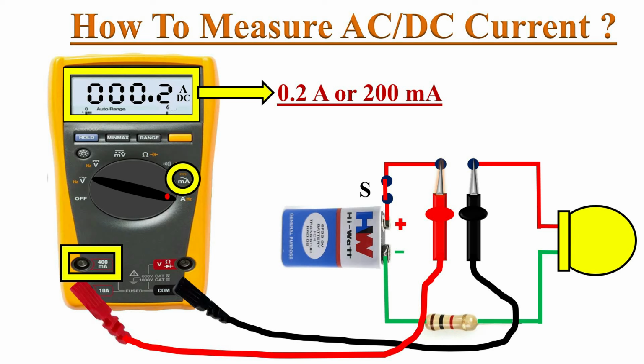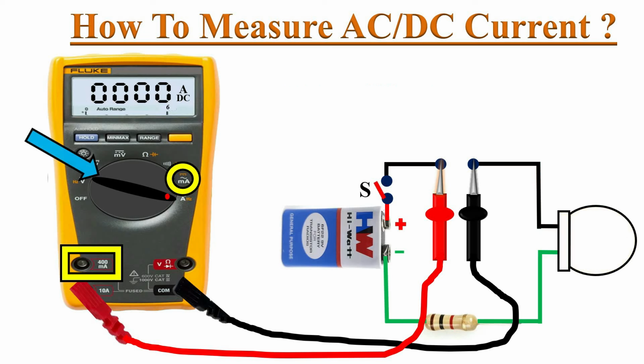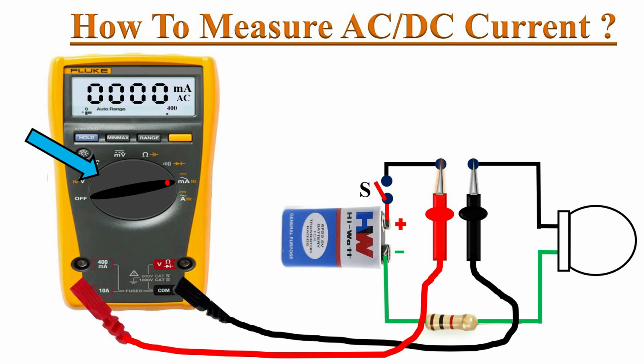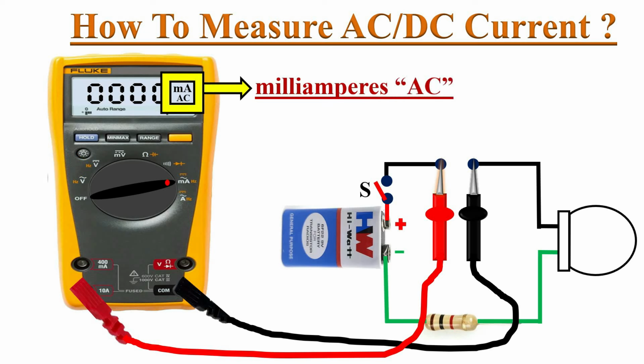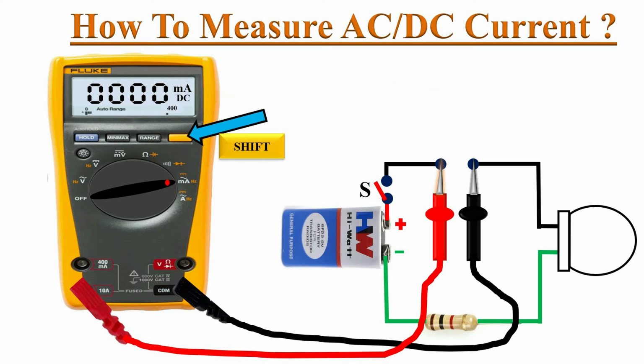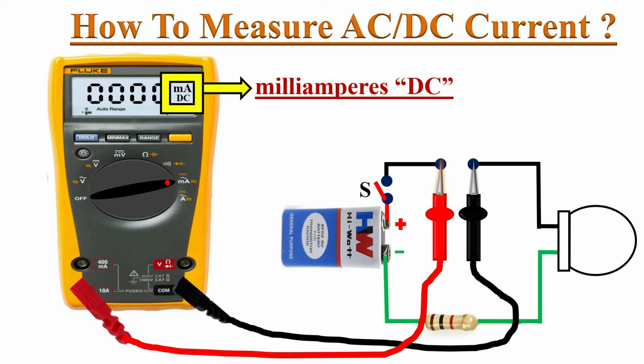To change the settings of the meter, first we must switch off this circuit. Turn the dial to milliamperes position and change red test probe to 400 milliamperes port. First change the dial's position to milliamperes. On the display we can see milliamperes AC symbol, but here we are measuring DC milliamperes. To change into DC milliamps, just push shift button. Meter changes it to DC milliamperes measurement mode. We can see the symbol on display.